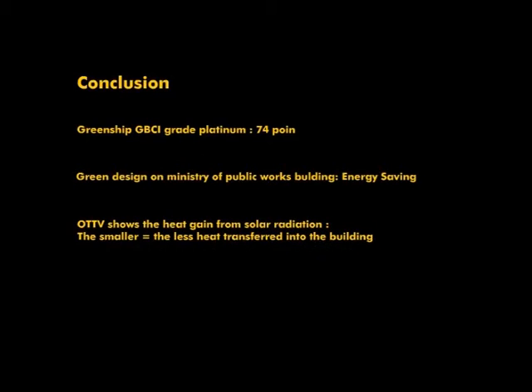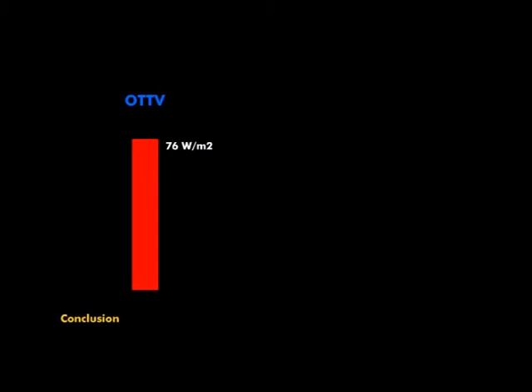To summarize, the thermal performance of the building envelope, or its overall thermal transfer value, was reduced from 76 watts per square meter to 28 watts per square meter with the new design. This value is well below the maximum limit regulated by the DKI government, which is 45 watts per square meter.